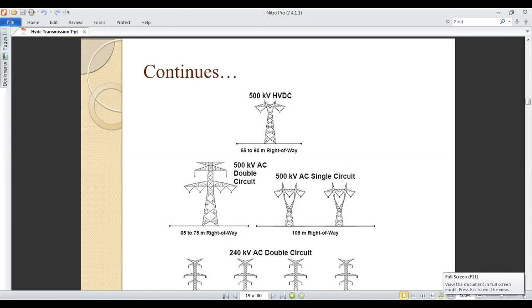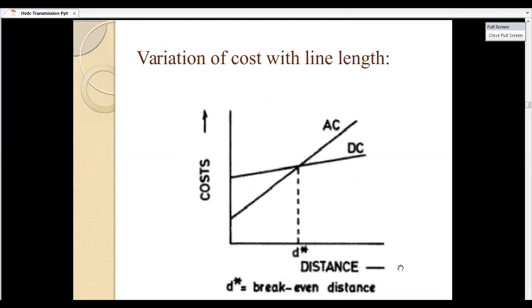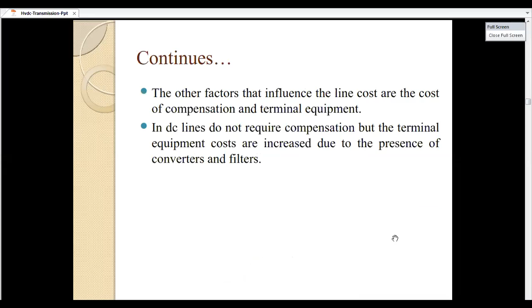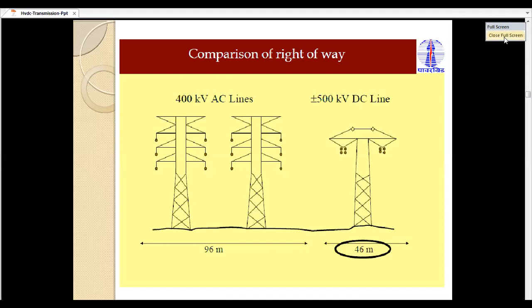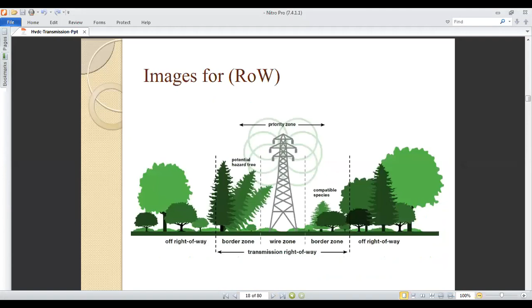Next, in the case of a 500 kV HVDC line, 55 to 60 meters is the right of way. In the case of a 500 kV AC double circuit, it requires 65 to 75 meters of right of way. In the case of a 500 kV AC single circuit, it requires 105 meters of right of way. That means the total space in between. And in the case of a 240 kV AC double circuit, 185 meters is the right of way.